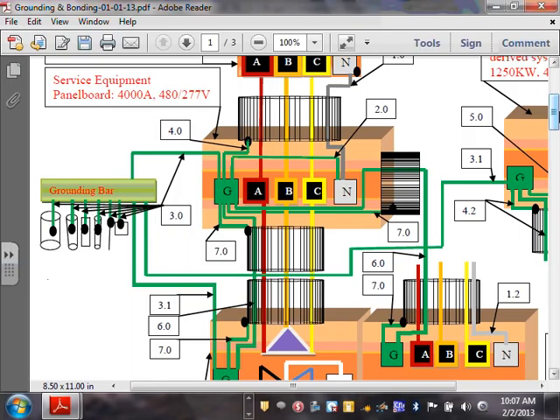So I grounded all my conduits. How do you do that, right at this point? You have two options. You have 11 of them, right? You have 11 conduits coming from the bottom, underground. How do you guys do it? You daisy chain them. Yeah, you can do two methods. Either you daisy chain them, you take one to the other to the third, an unbroken daisy chain, right? Daisy chain 1, 2, 3, 4, 5, 6, all the way to 11, and take it all the way back to where? To my grounding bar inside the switchgear. That's, I think, the proper method.